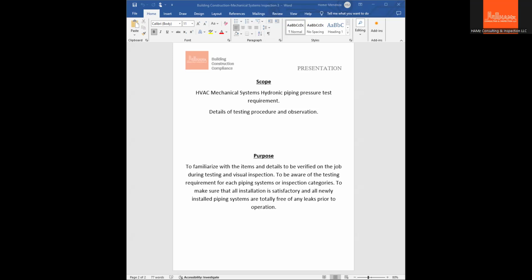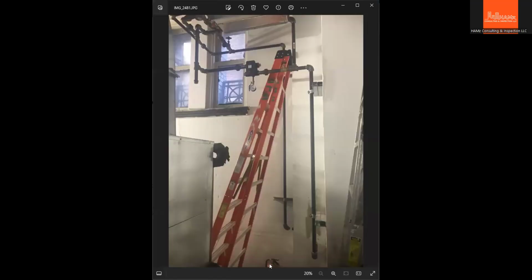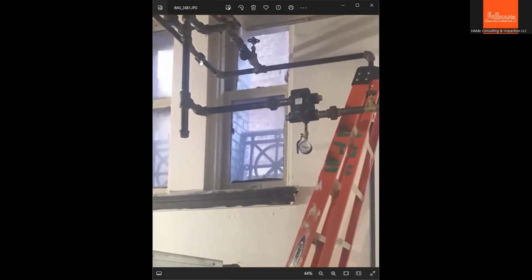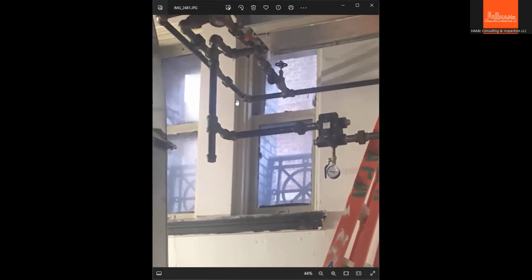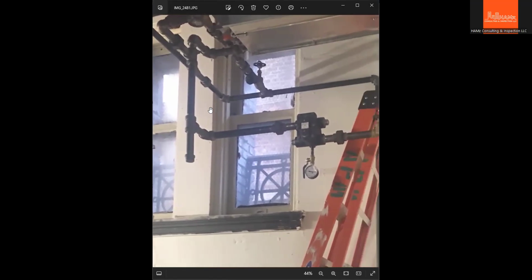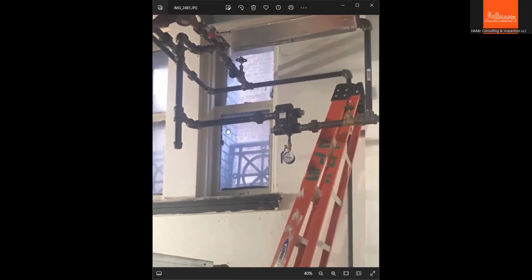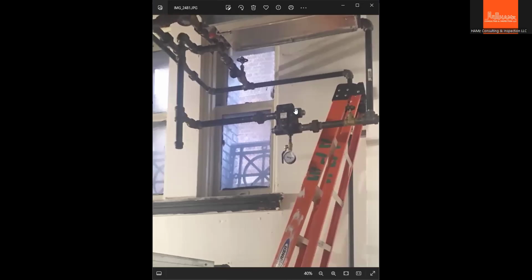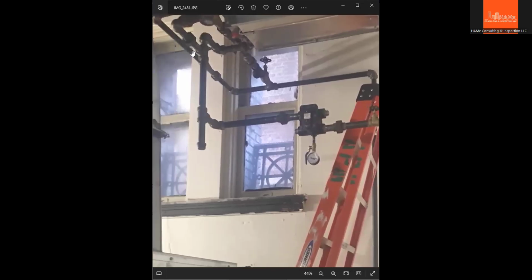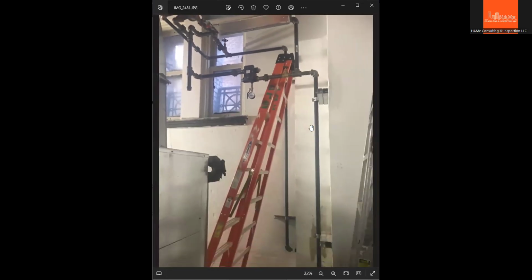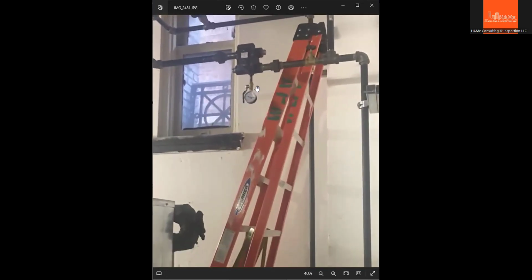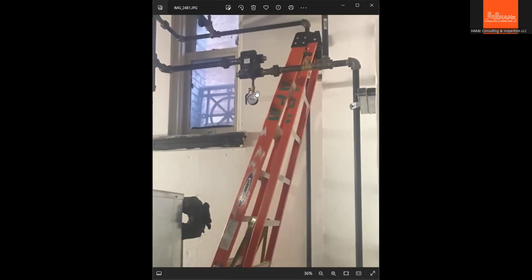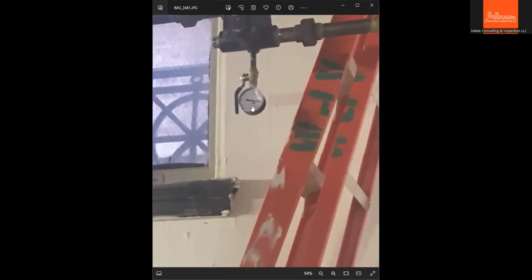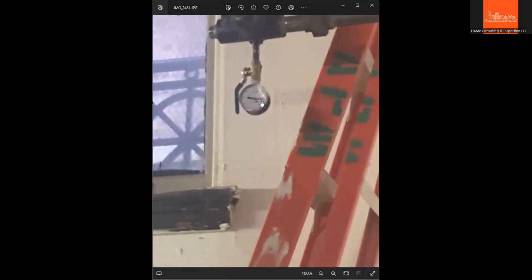The system I'm showing here is an assembly for steam piping. The test should be observed for 2 hours. That's the code requirement standard for every hydronic piping system. During the 2 hour test, you take a photo of the whole assembly where your pressure gauge is installed. That's the setup of the test, and you need to identify the reading of the pressure.